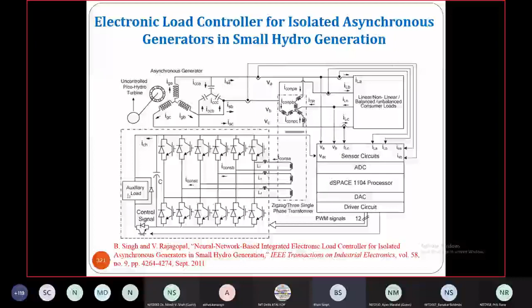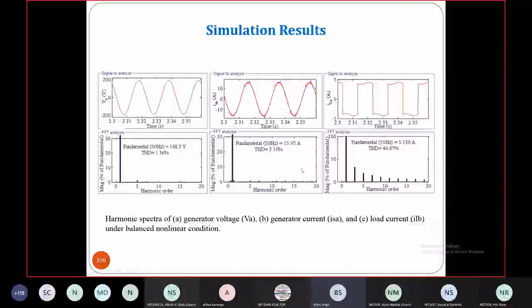And you can see the terminal voltage and the generator current. The load is unbalanced, and still your generator currents are not affected. It works very well. When load power is varying, it does not affect the generator current, because the load compensation takes care of that, and for unbalanced current and unbalanced load also, it works very well. The voltage THD still maintains 1.36%, and the generator current THD is 3 point something, but the load current THD was quite high, 46%, because of single phase.